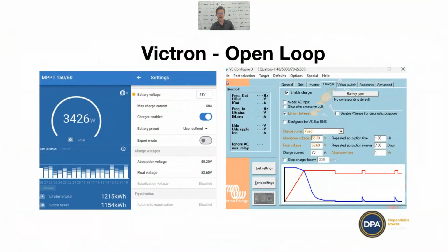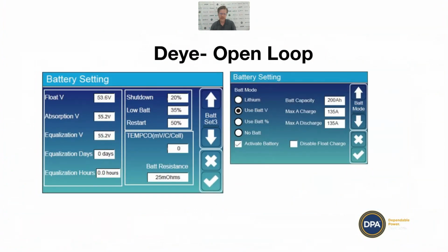So it's pretty straightforward doing it in open loop. The same is going to be true for Noark as well. So Noark and Deye, you're going to go and put the battery onto battery voltage. This is in the battery settings on the Deye, and then you're going to set it up, telling it it's 200 amp hours if it's a single Helios. And then you're going to go and set these float and absorption values as if it's a lead acid battery.